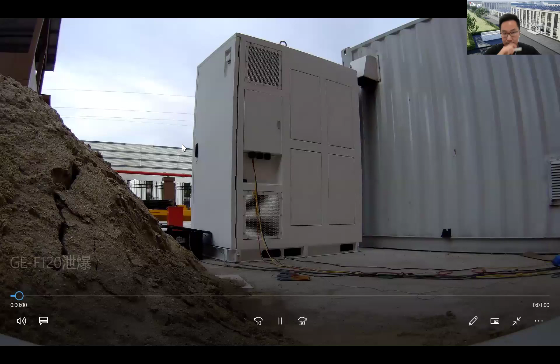What just happened is we manually triggered multiple cells inside this GE-F120, a previous generation of the 215, an older model. We triggered a sudden release of pressure within the cabinet, and you can see there are blowout panels built into the back to release the pressure so that the cabinet itself doesn't become a bomb, doesn't produce shrapnel, and the release of pressure will not compromise structural integrity.